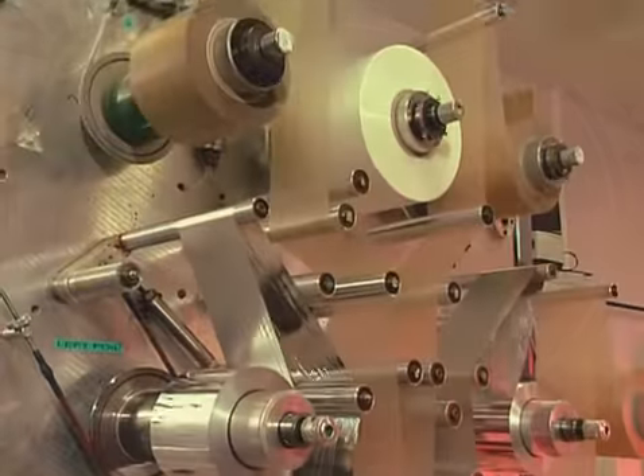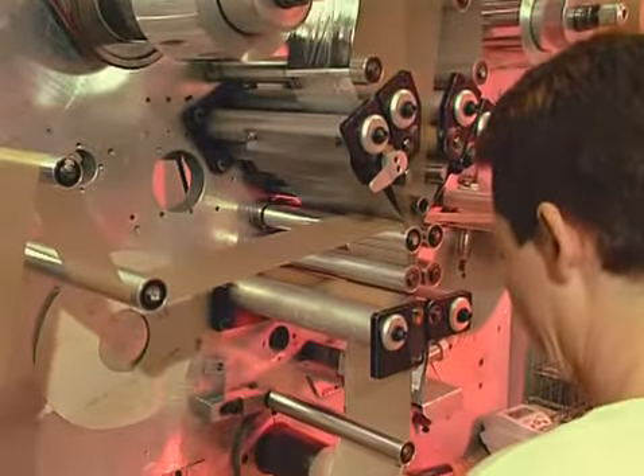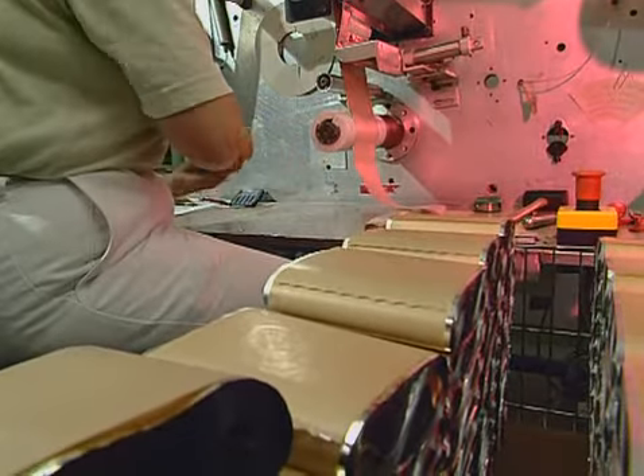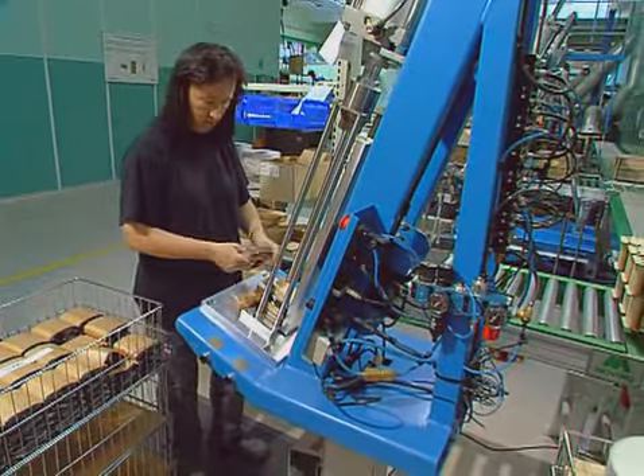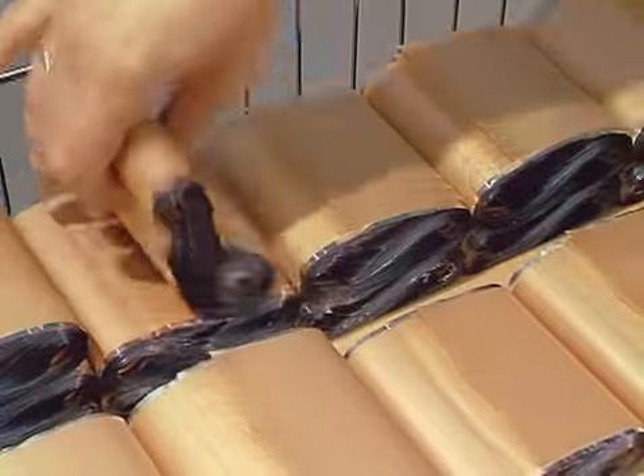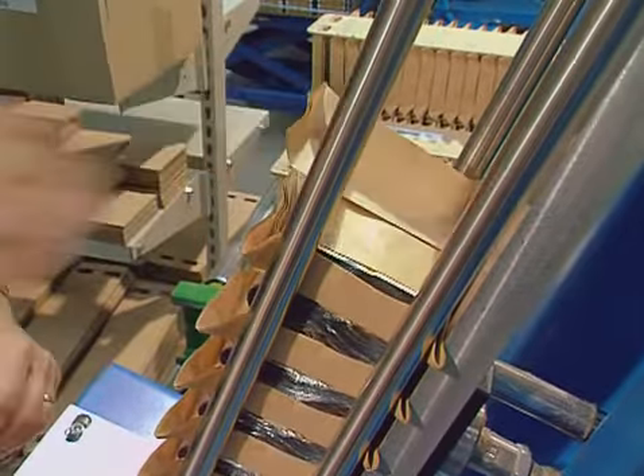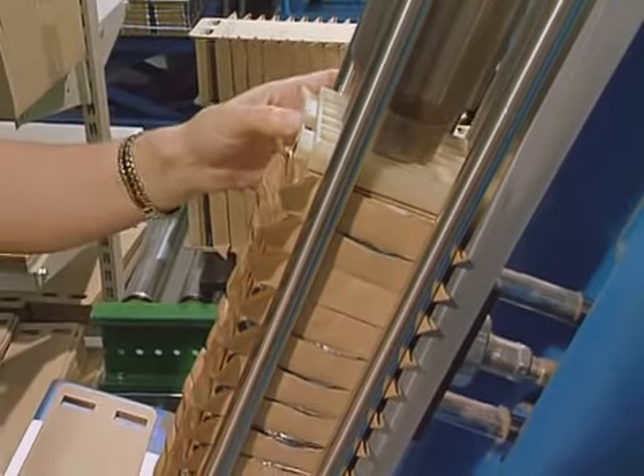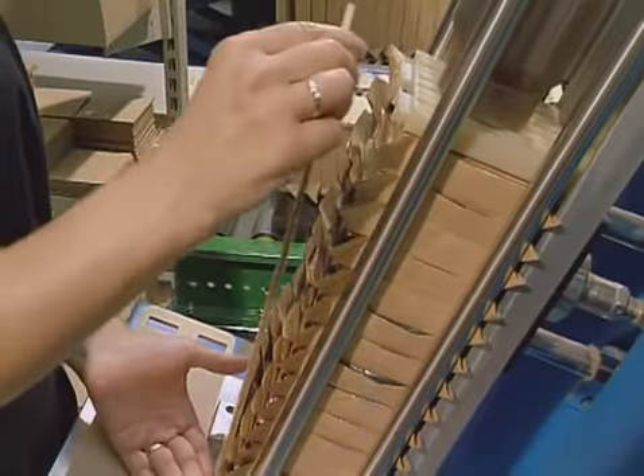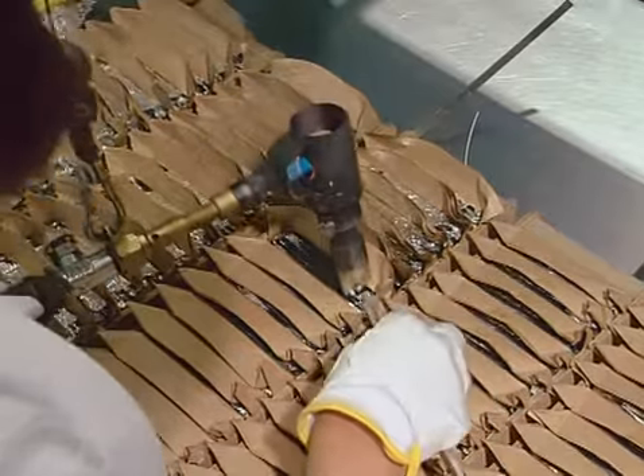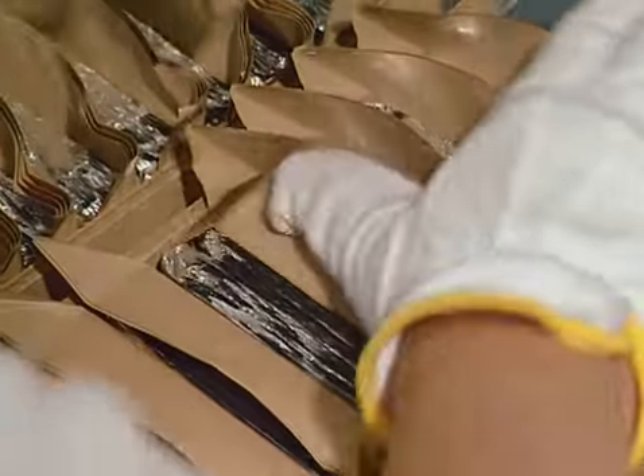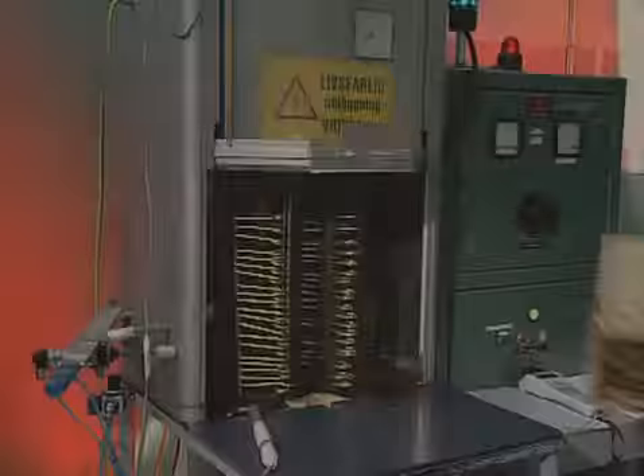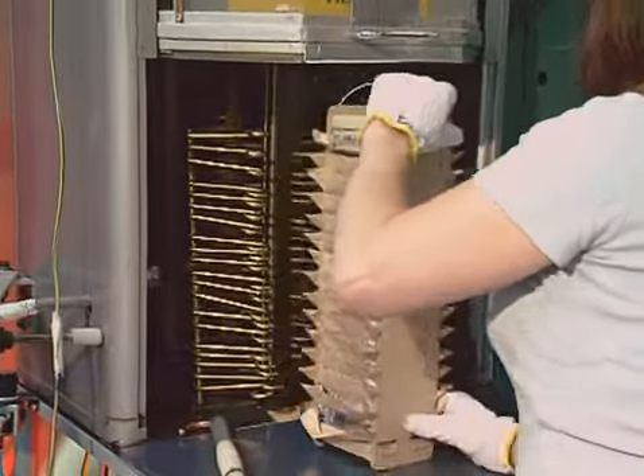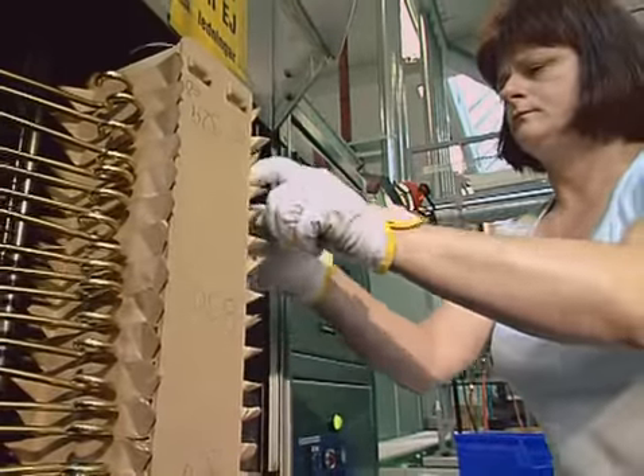The capacitors are manufactured of aluminum foil and have an insulation consisting of paper and plastic film. They are stacked with insulation distances in a package that is pressed together until the prescribed pressure is reached, thereby affecting the capacitor's capacitance. The single package is soldered together. Thereafter, every unit is tested in accordance with the applicable standards.